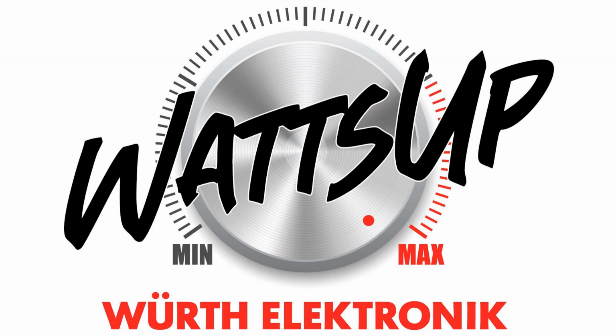So right now you see trace 1 and trace 2 with the 2 colors. I can still open other tabs because, as you can see, the receiver has 2 channels. So it means that I'm measuring the line and the neutral simultaneously, and with 3 detectors each. So I could, for instance, just to show you, open another tab, click the neutral, and put the quasi-peak detector.